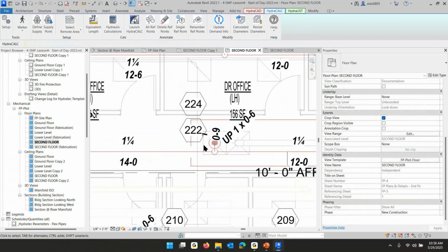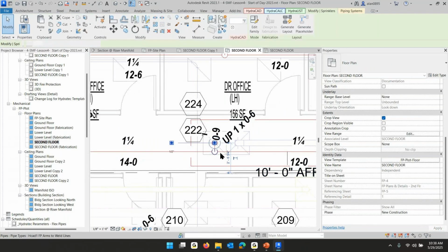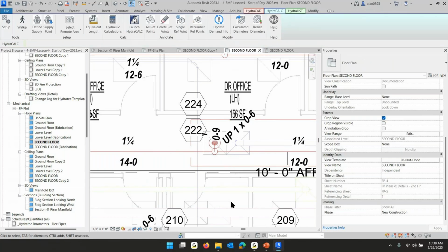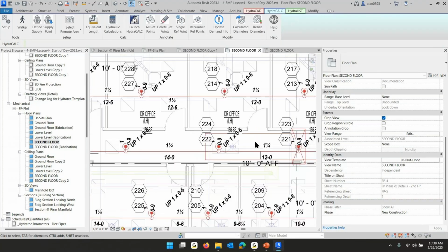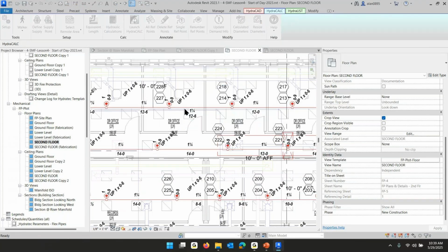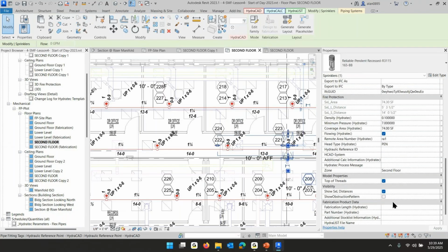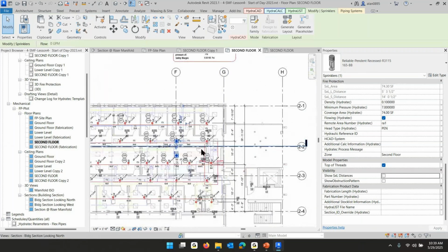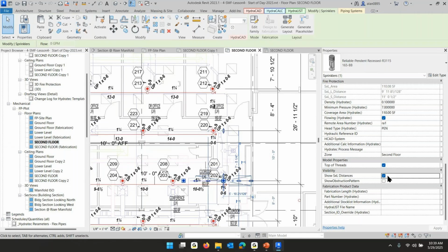Now, some people would say, geez, Al, I haven't ever done this. What's this all about? Why do I have to do all this work? The answer is you don't. You could just call them all 225, so long as you got enough pressure and the sizes are reasonable. If you don't have the pressure, you can make the sizes unreasonably big, or you can be more specific with the calculation and don't cheat yourself by saying they're covering 225 when they're not. So I'm turning those back off, and then I'm moving on to my next slide.